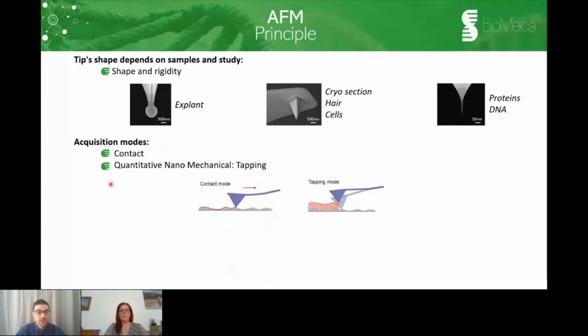The second mode is the quantitative nanomechanical mode or tapping mode. With this mode, it's very powerful because, as you can see here, the tip oscillates on the sample and hits it punctually. As in contact mode, we define a threshold force, and the piezomotor adjusts the position of the tip to keep it constant. Consequently, we obtain at first the topography of the sample, and then the biomechanics, because each pixel of the picture is a force indentation curve.